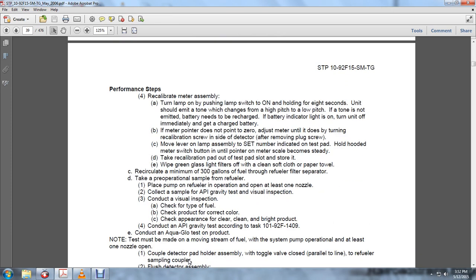Performance steps. Recalibrate the meter assembly. Turn on the lamp by pushing the switch on and holding it for 8 seconds. The unit should emit one tone, changing from high pitch to low pitch. If the tone is not emitted, the battery needs to be recharged. If the battery indicator light is on, turn off the unit immediately and get a charged battery.